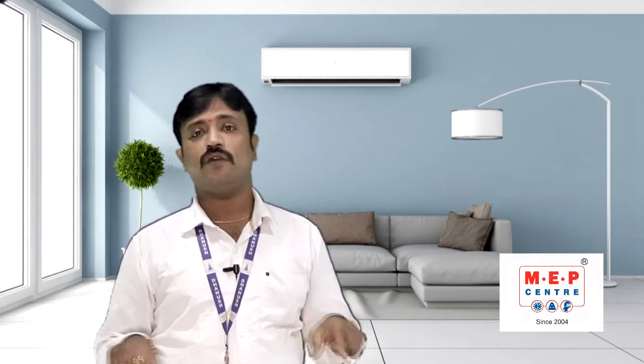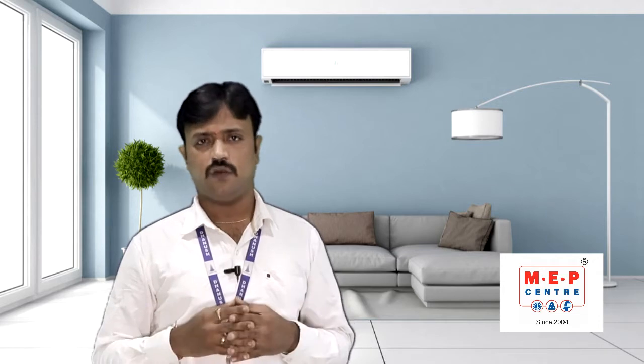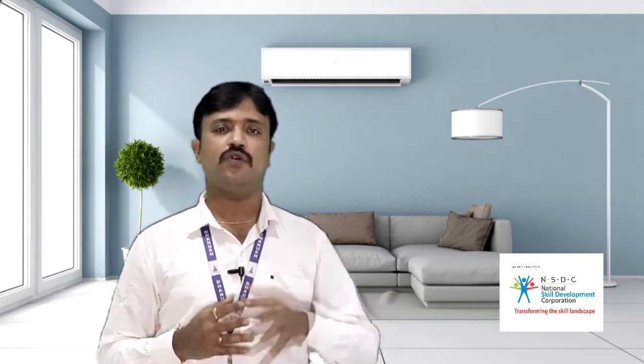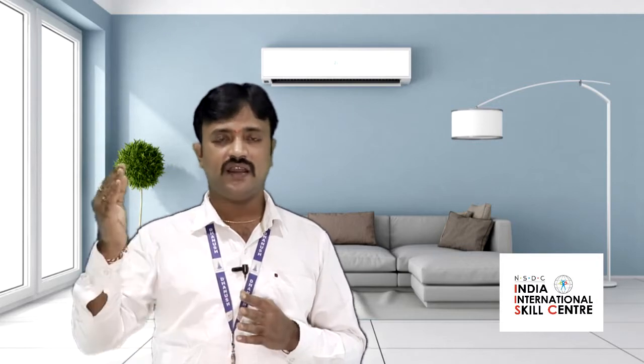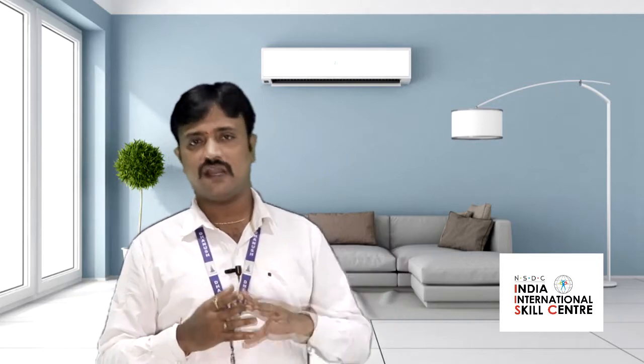Through this standard, for a small area, we find how much tonnage of AC we require. And here we are only doing the calculations for domestic cases, called split AC and window AC. We are not going to cover centralized systems, because we hand over the project. If it is centralized air conditioning, we hand the project over to HVAC engineers, and we directly take the load and put it in our transformer calculation. That is about the air conditioning loads.